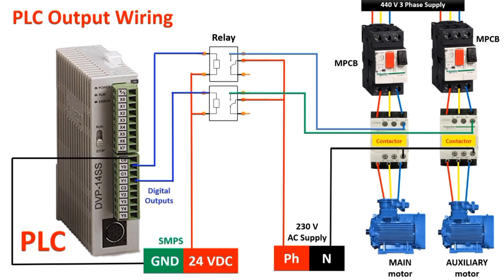Now let us understand the output circuit required for this project. First of all, in the common terminal we have to connect the ground terminal of the SMPS. Our actual output is the motor, but it is turned on by a DOL starter. This is the MPCB which works as both MCB and OLR, and this is our contactor. Since we cannot directly energize the contactor through PLC outputs, we have used a relay. In the relay input circuit, one terminal of each relay will connect to the 24V supply, and the other terminal of relay 1 will connect to the Y0 position.